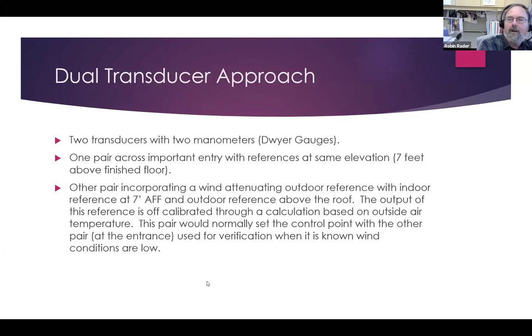One thing that we've done in this case is we've used 2 transducers and 2 manometers in buildings. In this case, one of the transducer combinations is across the important door, say at 7 feet. So the outdoor reference is at 7-foot elevation, and the indoor reference doesn't have to be at this entry. It can be well within the building, also at 7 feet.